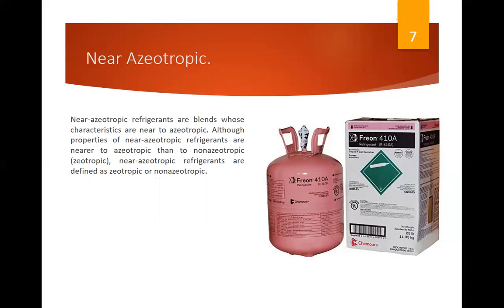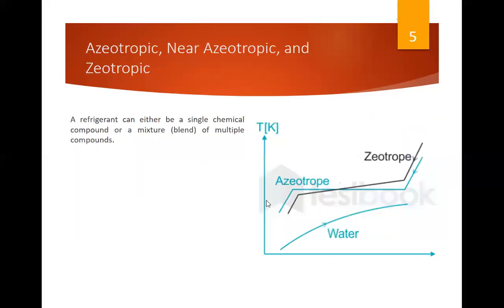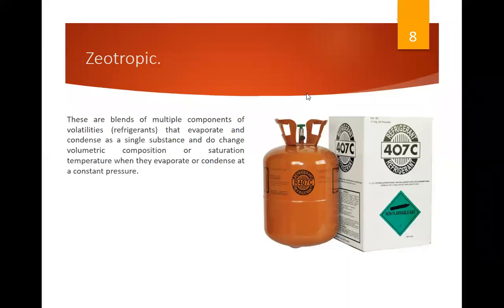Near-azeotropic. Near-azeotropic refrigerants are blends whose characteristics are near to azeotropic, although properties of near-azeotropics are nearer to azeotropic than to non-azeotropic or zeotropic. Near-azeotropic refrigerants are defined as zeotropic or non-azeotropic. So ito yung example, Freon R410A. Azeotropic. These are blends of multiple components of different volatilities refrigerant that evaporate and condense as a single substance and do not change volumetric composition or saturation temperature when they evaporate or condense at a constant pressure. So this is the example, refrigerant R407C.